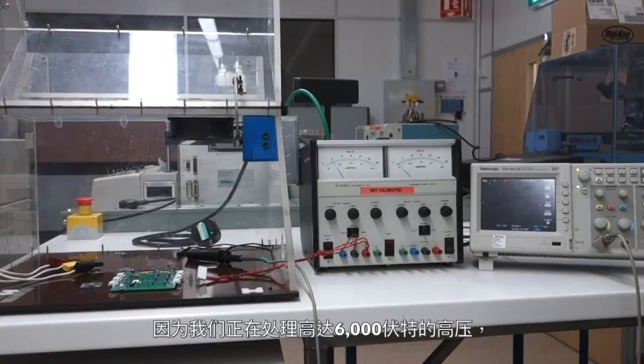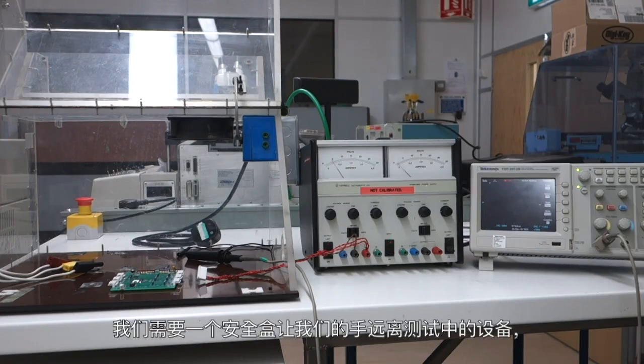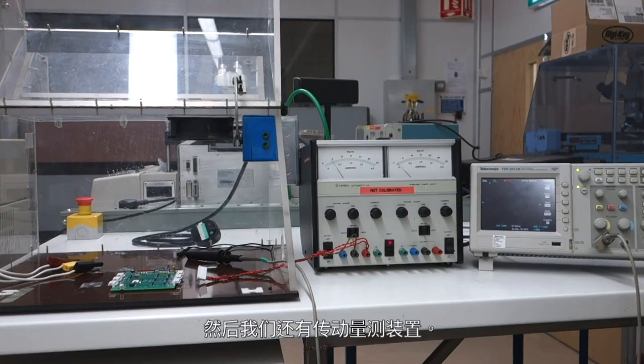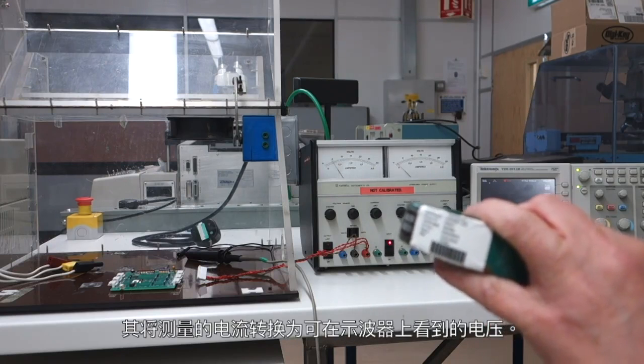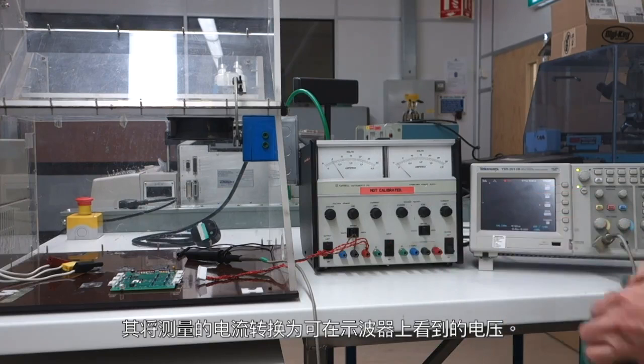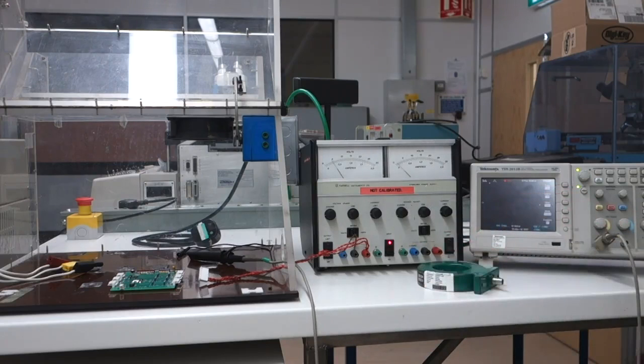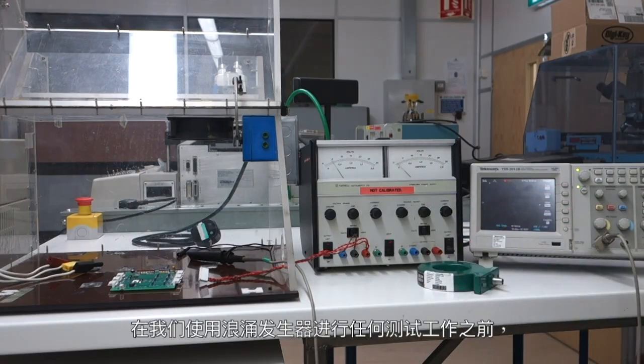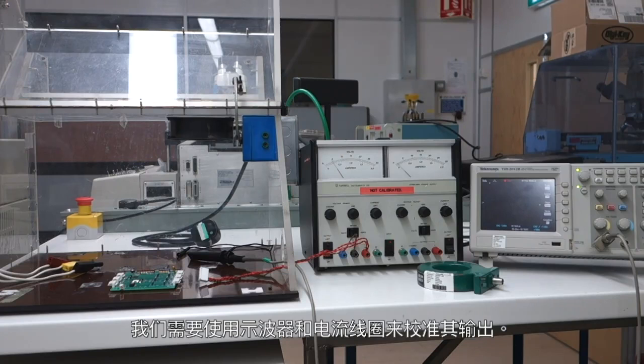Because we are dealing with high voltages, which can be anything up to 6 kilovolts, we need a safety box to keep our own hands away from the devices under test. Then we have the measurement gear itself. The key items here are the oscilloscope and a current coil, which converts currents measured into voltages that can be seen on the scope. Before we do any test work with the surge generator, we need to calibrate its output with the oscilloscope and the current coil.